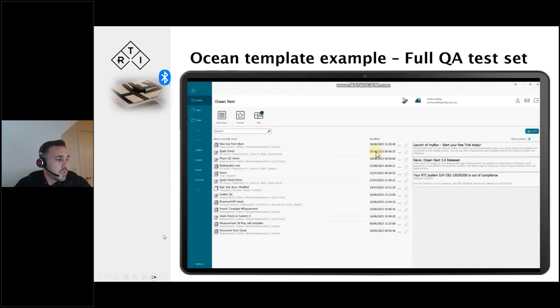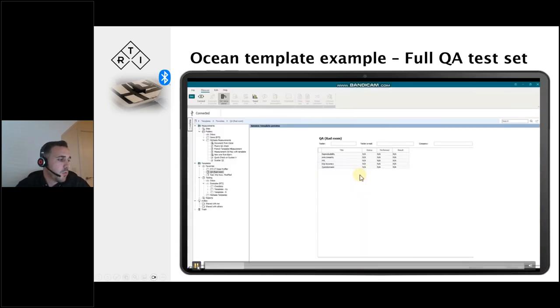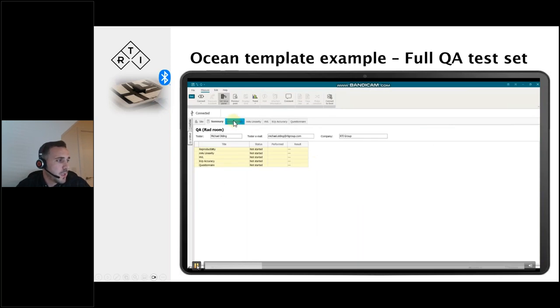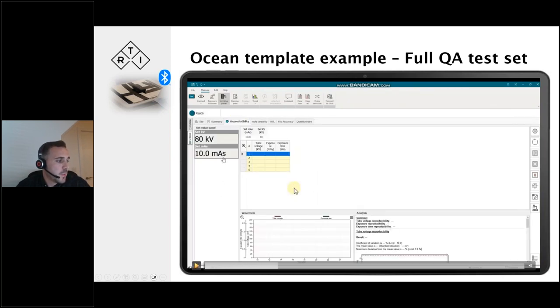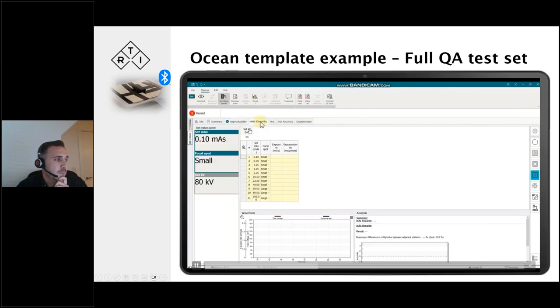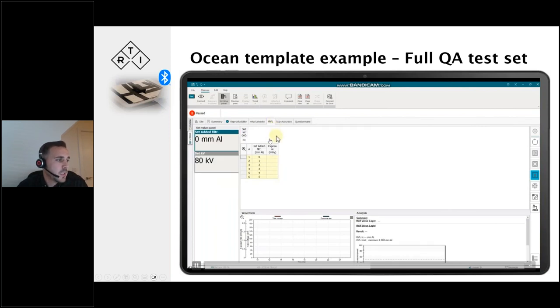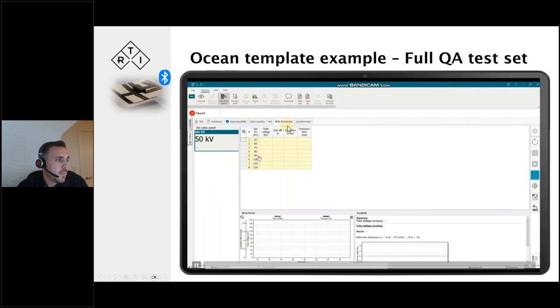Okay, so that's how easy a template is. In this demo, we're also going to do another one, for QA of a whole rad room, just as an example. Here you see within the template the typical tests you might be expected to perform as an engineer. Previously we showed KVP accuracy, but now we've got a reproducibility test, and we've also got mAs linearity. Again, everything's shown on the left-hand side for you to see, so you just make the exposures and everything's automated. There's also HVL tests, a KVP accuracy test, and then a questionnaire.